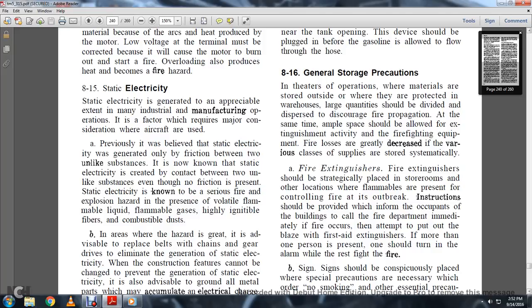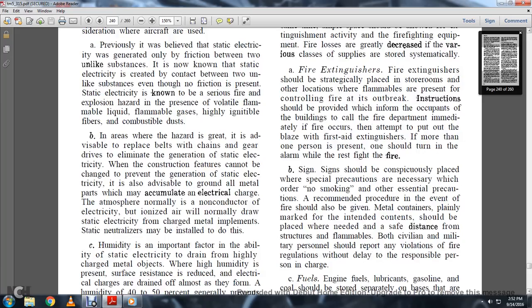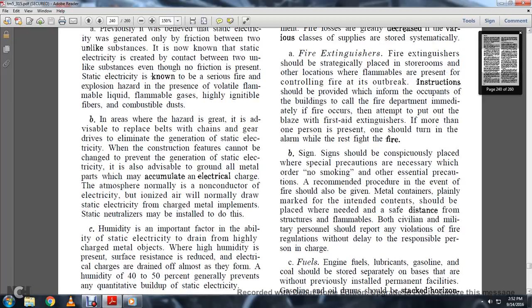Static electricity is now known to be a serious fire and explosion hazard in the presence of volatile flammable liquids, flammable gases, highly ignitable fibers and combustible dust. In areas where the hazard is greater, it is advisable to replace belts with chains and gear drives to eliminate the generation of static electricity when the construction features cannot be changed to prevent it. It is also advisable to ground all metal parts which may accumulate an electrical charge. The atmosphere is normally non-conductive electrically, but ionized air will normally draw static electricity from charged metal implements. Static neutralizers may be installed to do this.